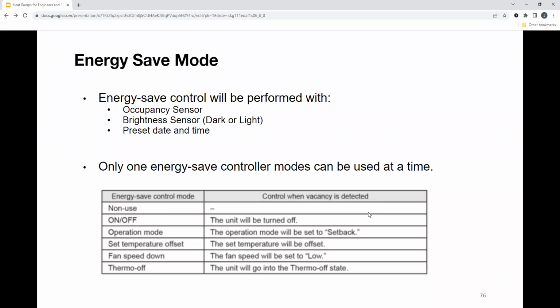So energy mode, or energy save mode, is pretty broad overall. What you'll need for this is either a local controller that has occupancy sensing, and there are local controllers with brightness sensing. There's also a way you can go through a central controller and preset and set a date and time for some of these functions. When you are doing energy save through a controller, you're only able to select one of these modes at a time. These are all available for you, I don't have to read through all of them. But some of the most common ones are set temperature offsets, for night setbacks. And then you are able to turn the fan speed down as well.